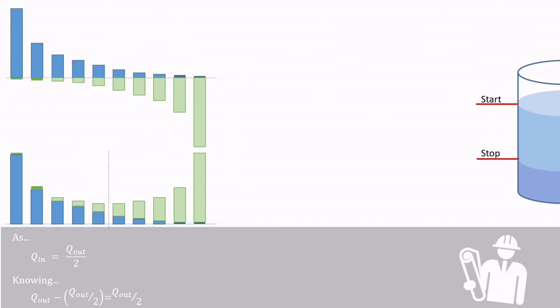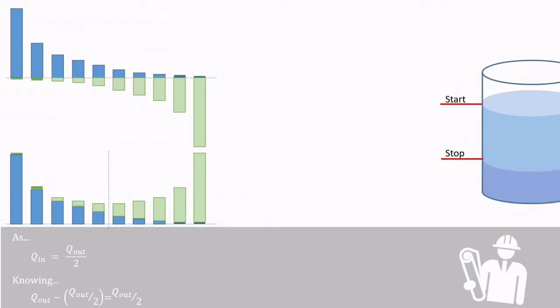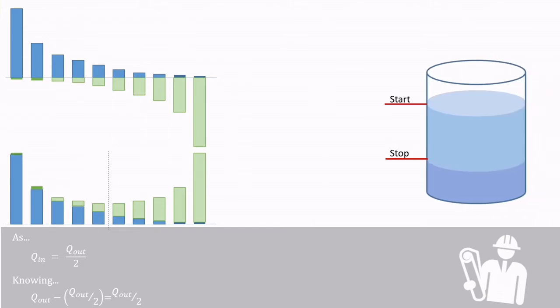When looking at this in terms of formulae, the time between starts or stops can be seen as the volume over flow in, which is the filling time, plus the volume over the difference in flow out and flow in, which is the emptying time.